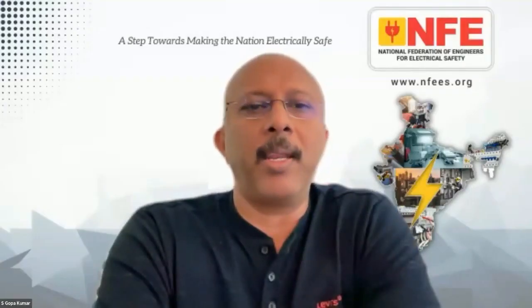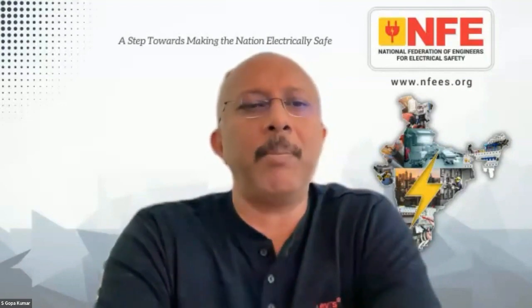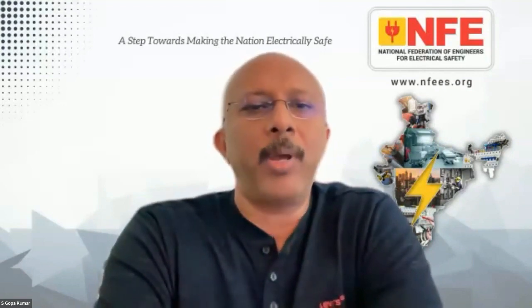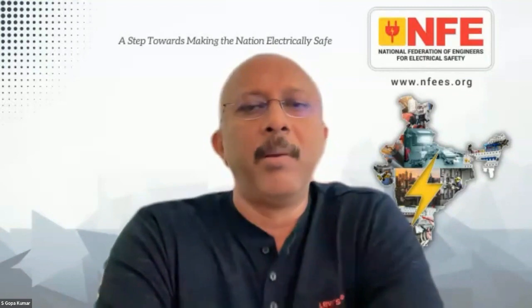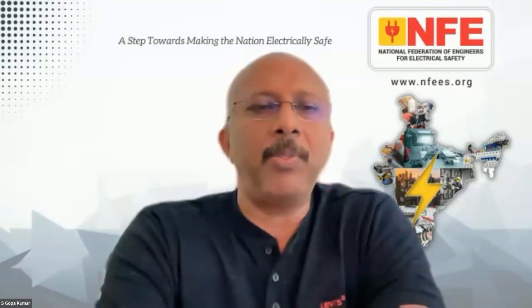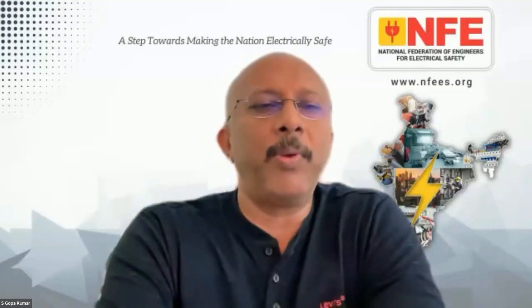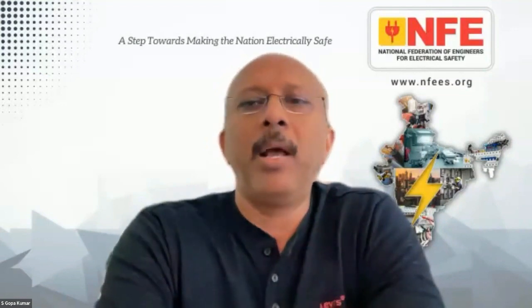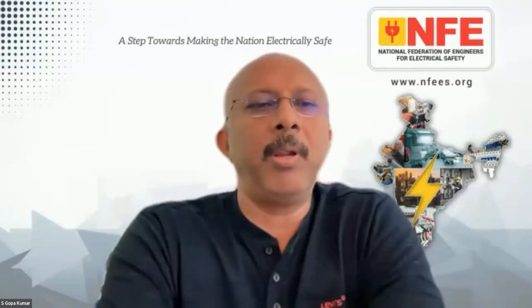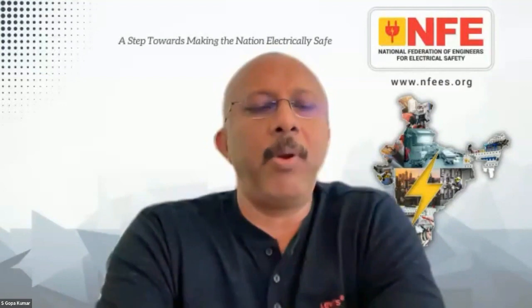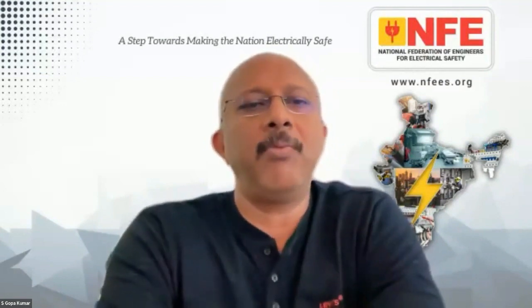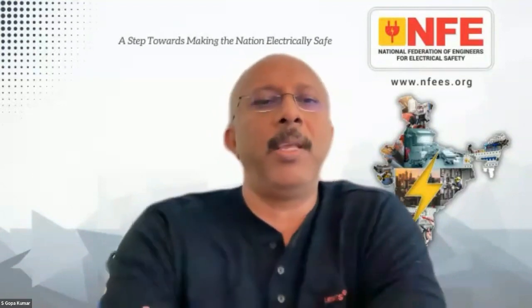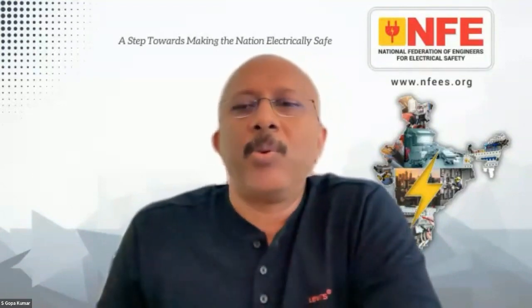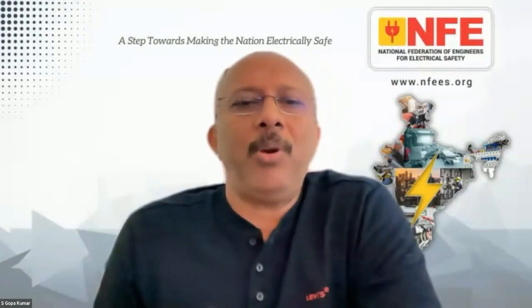New standards say the functional earthing needs a zero reference potential, and now the standards are saying the functional earthing has to be separate from the protective earth. So as a result, if you look at ISO 30129, more information can be found. But here in the Indian context, the problem is everybody wanted to have less than 1 volt between neutral and earth. Then my question is, if you have an IT system between the distributed neutral and the earth, probably the voltage is 150. Still the system works. And the system has to work, especially in hospitals, for example. So this 1 volt is technically not actually applicable.